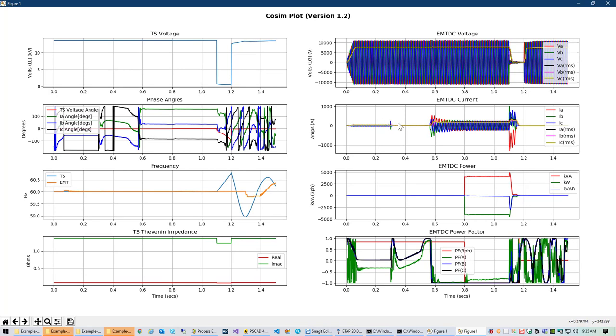Looking at our additional charts, we can clearly see from our first case where the fault was applied on a bus with lower impact — the wind turbine essentially rides through the fault and recovers in the system. For the second case, with the fault applied closer to the turbine with a larger magnitude and longer duration, it was unable to stay connected and tripped. In summary with ETAP20, you can add the ability to perform electromagnetic studies such as switching transients, ferroresonance, insulation coordination, sub-synchronous resonance, or use the EMT COSIM module to combine ETAP network model and transient stability with detailed power electronics modeling available in PSCAD.